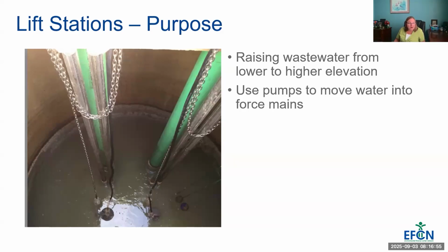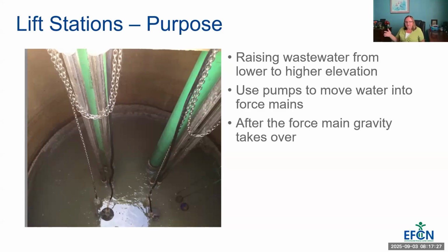I've got another comment: to convey sewage to a treatment plant. Yep, so oftentimes right before the treatment plant, there's a lift station. That's typically because our collection system is gravity, and that means it's running downhill regardless of the terrain, so it can get pretty deep. Then we have to lift that water up into the headworks of the treatment plant, or whatever our first stage of treatment is. After that water is pumped, it goes into the force main. After the force main, gravity takes back over. If you pump into the next manhole, then it returns to gravity flow. So the last note there is that the purpose is to raise the elevation, that it uses pumps, and then it returns to gravity.